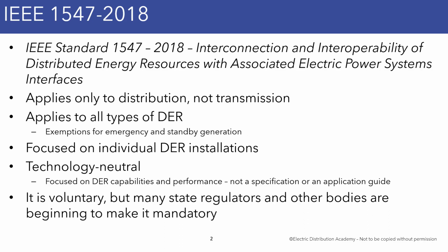1547 applies to all types of DER, solar PV, or fuel cells, or synchronous machines, what have you. And there are some exemptions for emergency and standby generation in terms of the different requirements that those types of generators have to follow. There is no size limit.